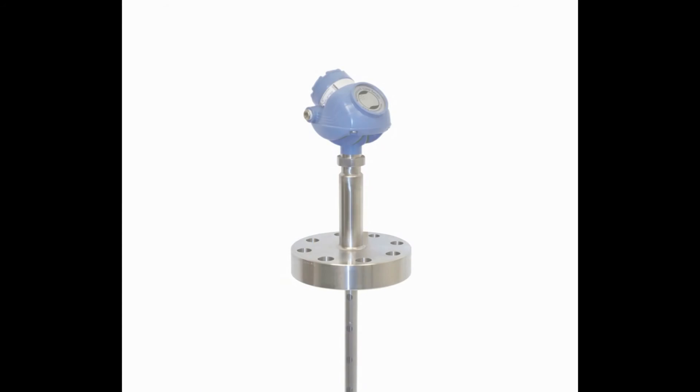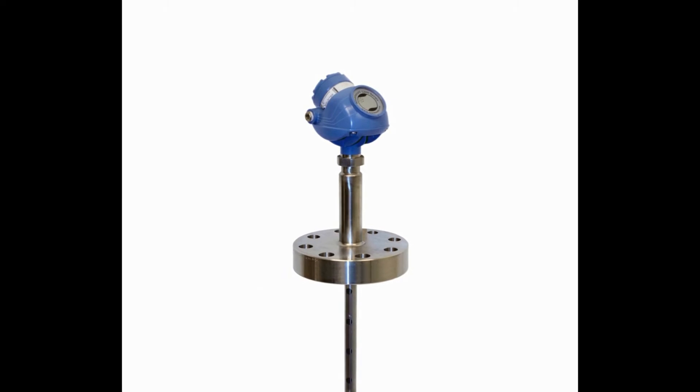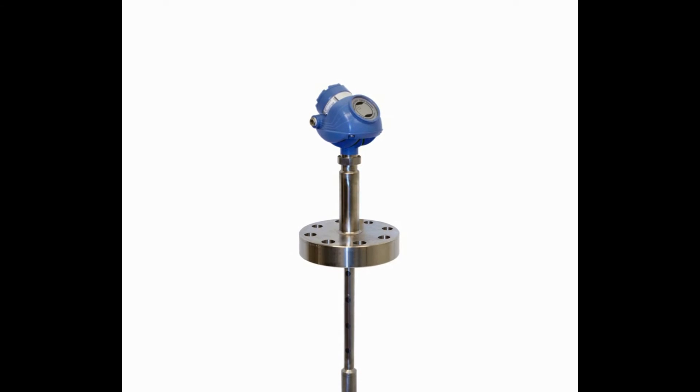The function of dynamic vapor compensation in the 5300 guided wave radar dynamically compensates for changes in the vapor space dielectric, minimizing accuracy errors associated with the effect of pressure and temperature changes.